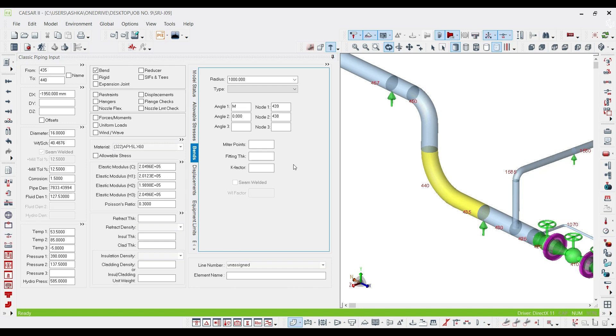But what about fitting thickness? What is it? In some cases in piping systems, you might have a fitting with higher or greater thickness than the adjacent pipes. In this case, you have to specify that thickness for the software because it heavily affects the ovality of your fitting.